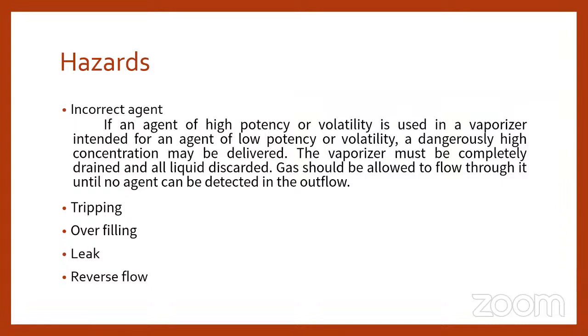If an agent of high potency or volatility is put in a vaporizer for an agent of low potency or volatility, a dangerously high concentration may be delivered. The vaporizer must be completely drained and all liquid discarded. Gas should be allowed to flow through it until no agent can be detected in the system. Tipping: whenever we fill the vaporizer chamber, some amount of liquid might enter into the bypass chamber where the fresh gas flows. So the first breath that the patient takes will be very highly concentrated. The next will be normal. Overfilling might cause a leak of the system, and the other hazards are leak and reverse flow.